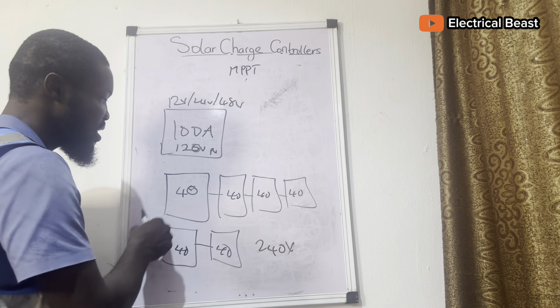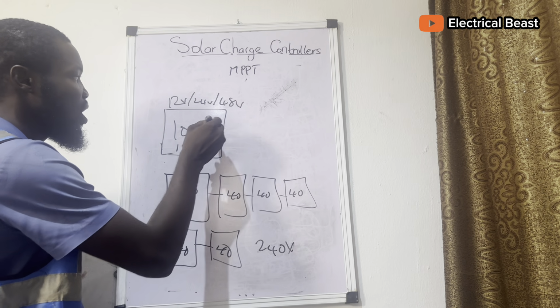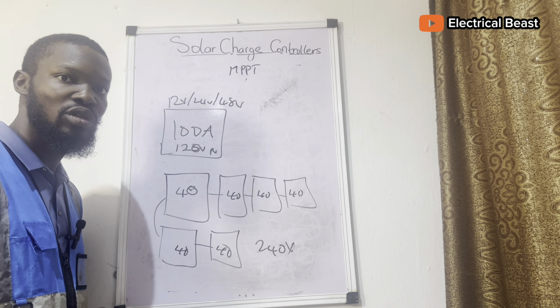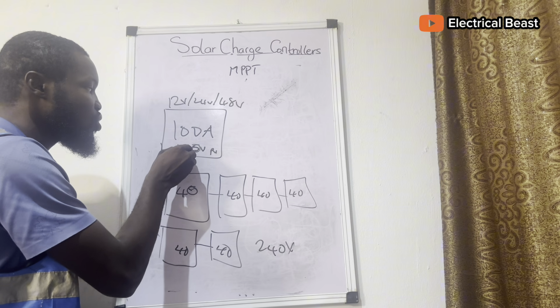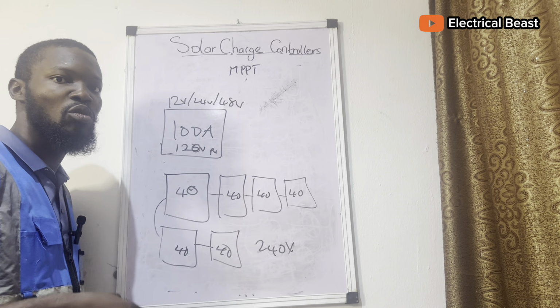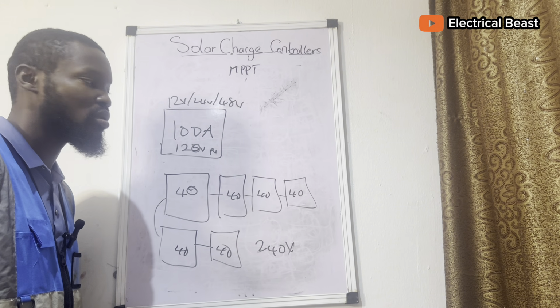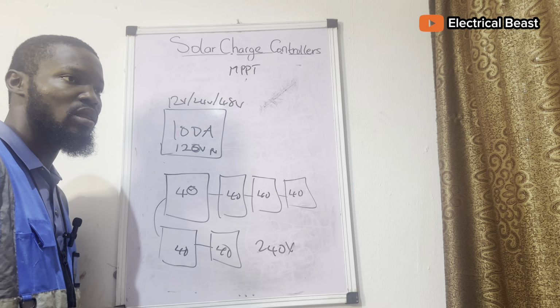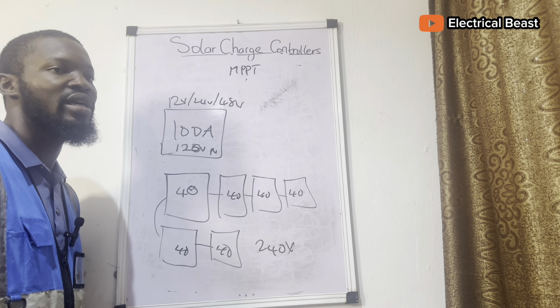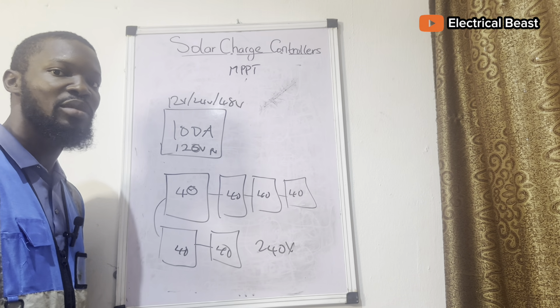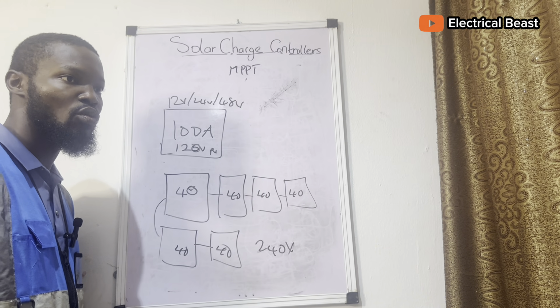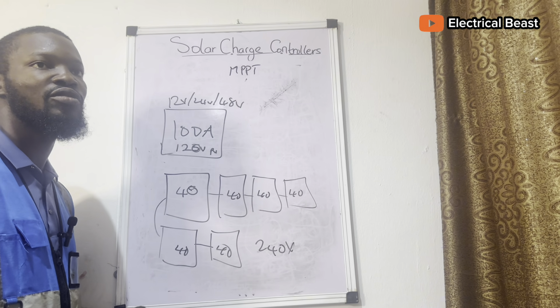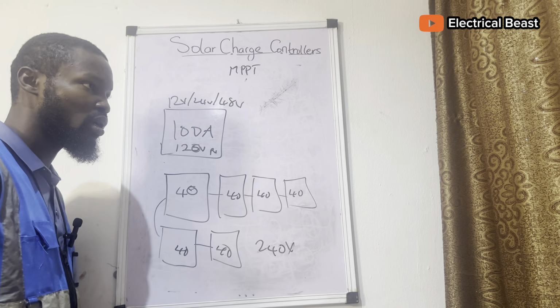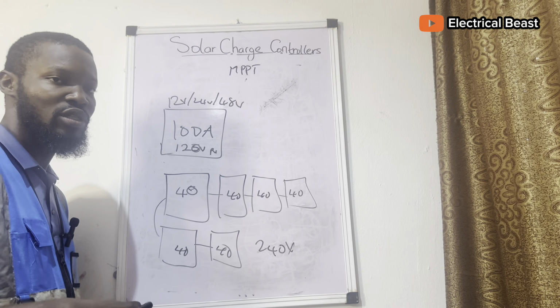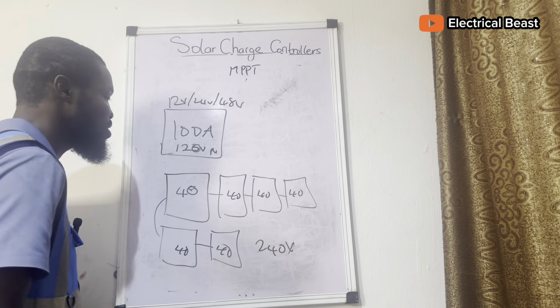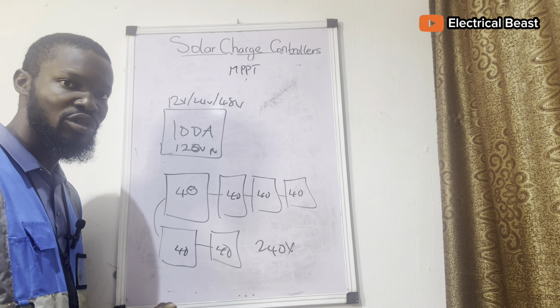So when you connect everything here in series to your MPPT charge controller, it's going to burn the charge controller, because it's above the voltage range that is written here. That is why most times a lot of installers have problems with this kind of connection. Now you would think, okay, because you've been using a hybrid inverter, and hybrid inverters accept this kind of connection. When you need to change to a controller, and you don't go up there to rewire the connection for the solar panels, you connect it directly to an MPPT controller, you are going to burn the controller.